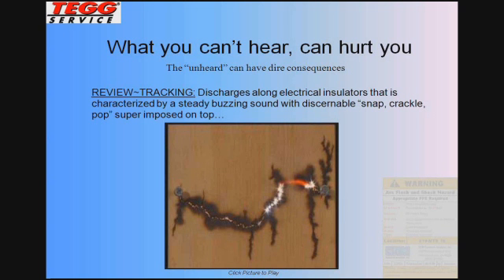The characteristic sound from an aural standpoint of tracking, as you may have heard on your sound files, would be a buzzing sound with a snap, crackle, pop superimposed on top of that as these discharges occur. I equate it to Rice Krispies. So when you hear that, it can be very alarming. Does infrared see tracking? The answer to that is no.